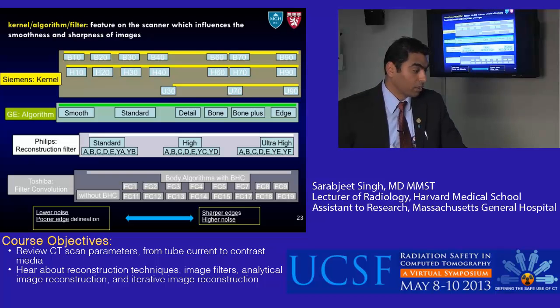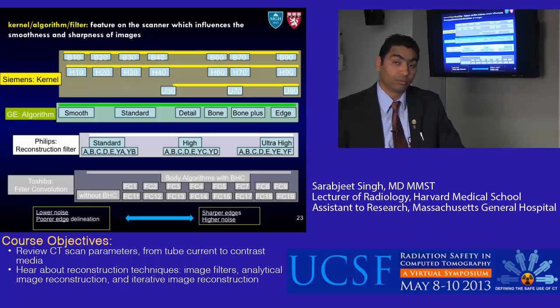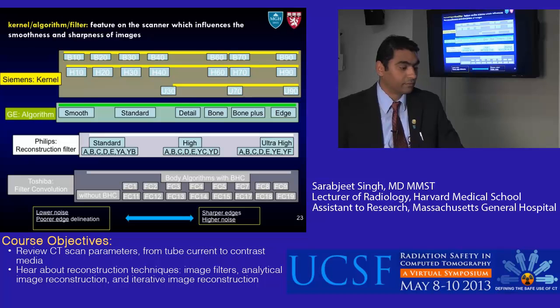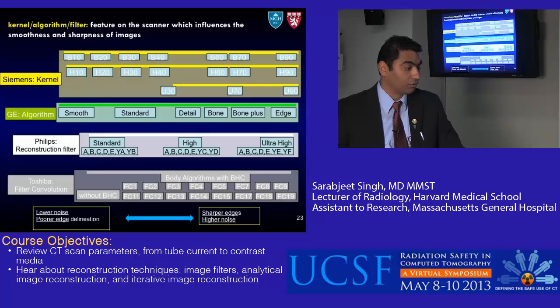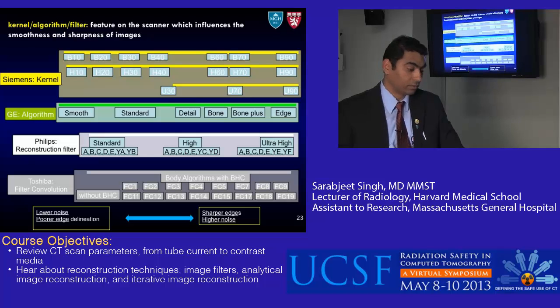Toshiba calls them filter convolution. Looking at Siemens kernels, they include various numbers for body and head from B10 through B90. GE names them smooth, standard, detail, bone, bone plus, or edge — intuitive names where an edge filter gives sharper edges. Philips reconstruction filters are grouped into three categories: standard, high, or ultra-high, with further nomenclature within each. Toshiba filter convolutions also have body variants and options without beam hardening correction. The key message is that it's important to know where a kernel lies in the smoothness-sharpness spectrum, because image noise can be lower or higher depending on which kernel is selected.